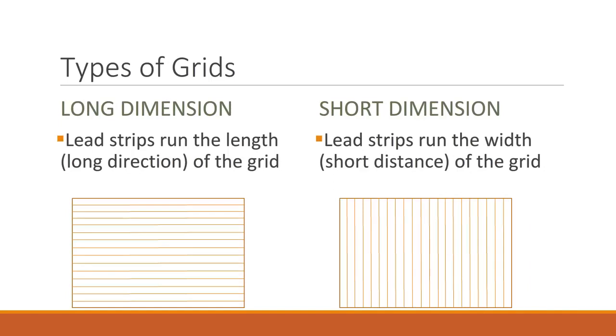Grids can also vary in the direction the grid strips run. A long-dimension grid is the most common grid and the lead strips run the length or long direction of the grid. A short-dimension grid is one in which the lead strips run the short distance or width of the grid. Short-dimension grids are useful in landscape mobile chest radiography on larger patients since the angle of the central ray is often not able to be perpendicular to the gridded image receptor but instead angled downward or caudal. This caudal angle will work with the lead strips rather than against the lead strips.